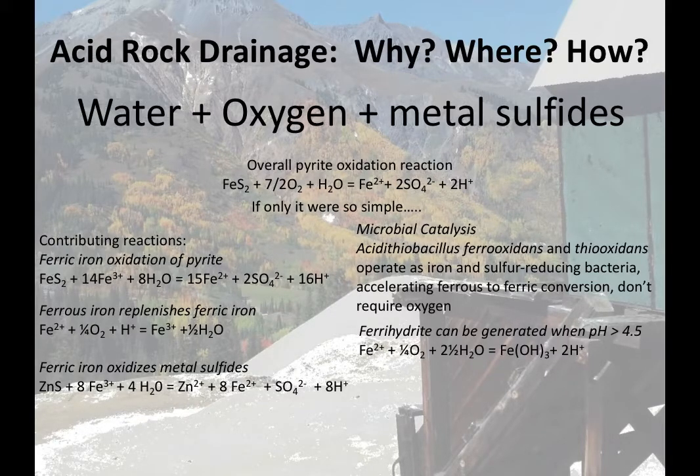You can also get ferrihydrites that start to form. So this one is a real bugger, because when you're Fe2+, you want the iron to complex with oxygen, ideally, or hydroxides, or whatever it may be, and come together as a solid. So when you see it all by itself, it's a dissolved ion, very, very small, very, very difficult to remove. As they start combining with other components, such as the hydroxide in this one, they start to get bigger, and we can pull them out.